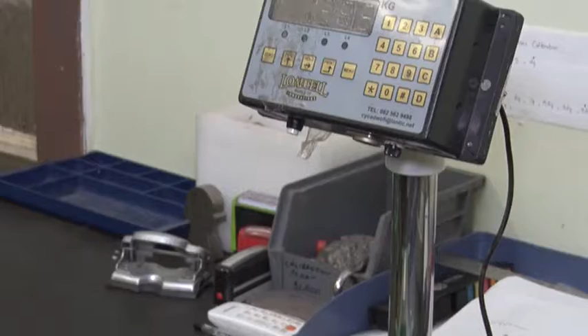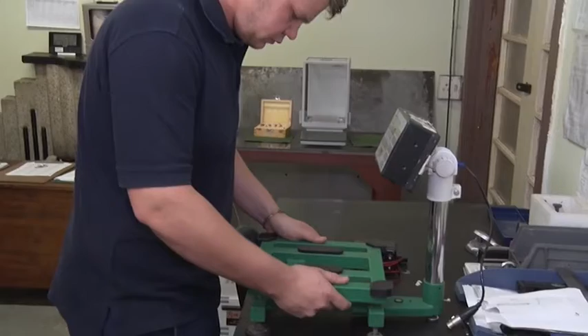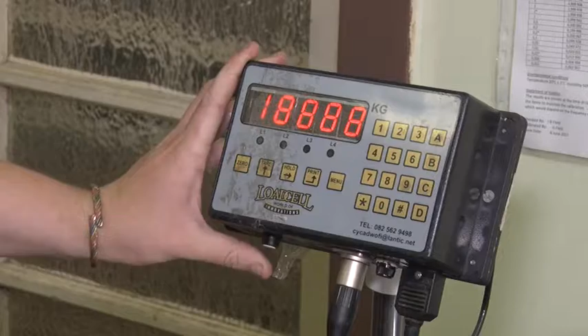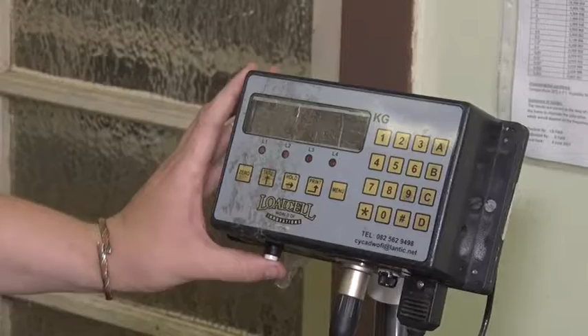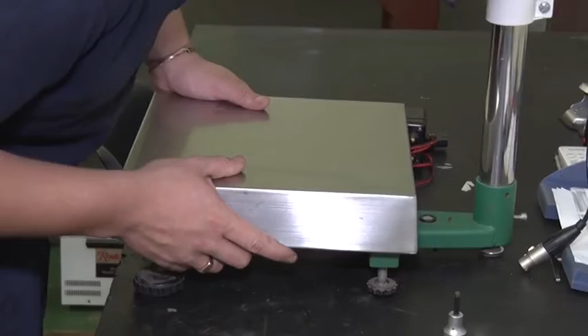Repairing and calibrating instruments is done here in the lab as well as on site, where equipment might be immovable. There is often much troubleshooting and problem solving when on site. There are 3 parts to a weight scale: the feet at the bottom, which balance the scale, the load cell, the measuring instrument within the scale set to output the measurement, and the load receptor, the plate that you put the load onto. Here, the scale fitter assembles the scale.